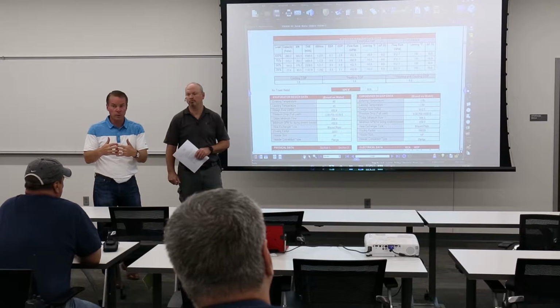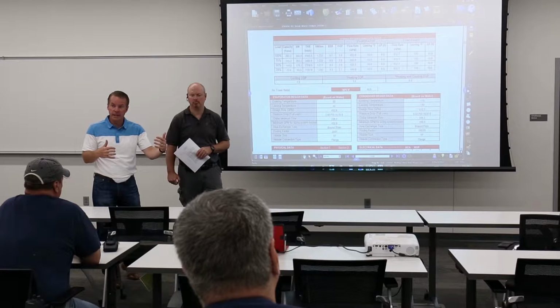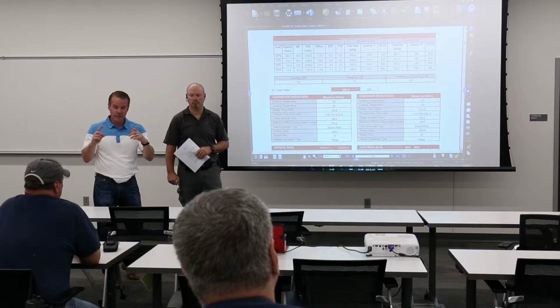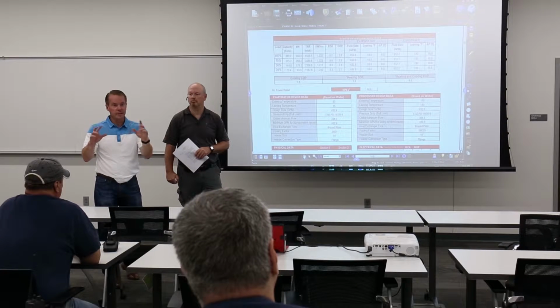So you're going to get 45 degree water off of the chiller, and it's there to supplement the campus chilled water system. That's the real intent of this chiller. Anytime campus chilled water is available, it's a heater for your dehumidification loop, your heating loop, with byproduct chilled water. Anytime campus chilled water is not available, then the chiller is a chiller. So in those times in November or December or February, when you have a spike in temperature outside for a couple days where you can't use free outside air but you actually need cooling, but you don't have campus chilled water available, then this is your chiller. This is your chilled water for helping to cool the building back down. So just think of it that way.